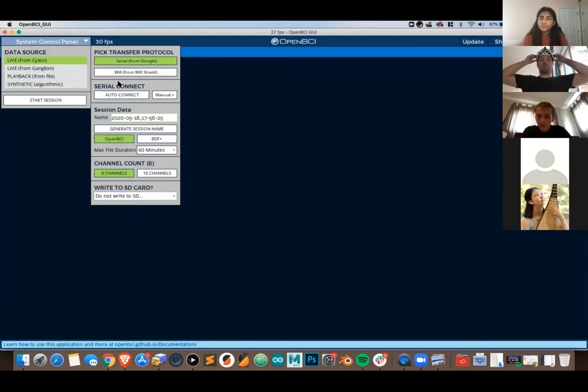So what I'm doing now is I'm putting the headset on, and this headset is configured with 8 electrodes, which are 1, 2, 3, 4, 5, 6, 7, 8. So they're arrayed around my scalp, and then there are a couple of extra nodes that you can twist into place for comfort. And then these guys here, I will explain what they do in a little bit, but they are the reference and the bias signals of the EEG system.